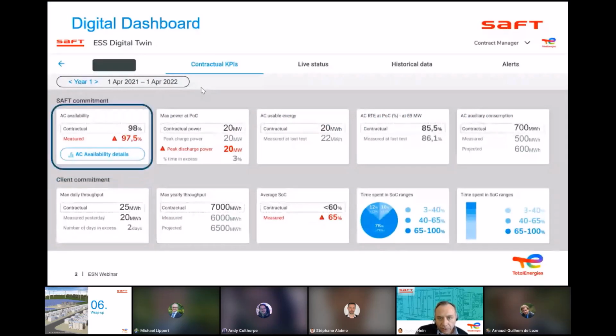In September of 2021, our monitoring system alerted us of a power limitation, as can be seen in the dashboard. The overall battery system power should be 20 megawatt with 20 megawatt hour of usable energy. However, the measured usable power at the storage facility had dropped by 0.5 megawatt, corresponding to a power availability of about 97.5%.